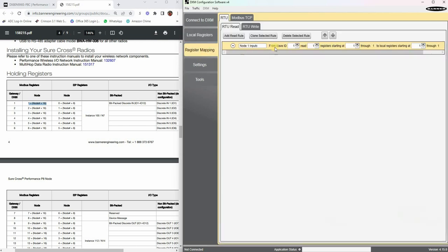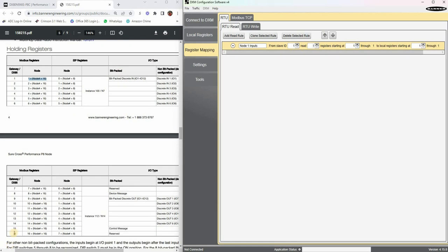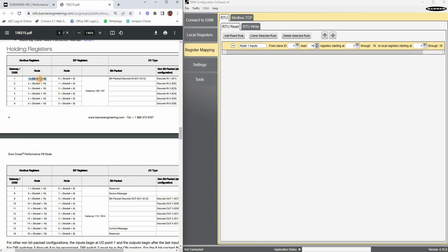So we're going to keep everything at 1 right now. Slave ID 1. We're going to read, looks like we have 16 total registers, we're just going to read all of those so we're going to type in 16 here. And then we're going to start at this address that's on the data sheet for those inputs. They actually start at this address right here. So if my node number is number one, then I'm going to times that times 16 and I'm going to add 1, and that's going to give me a value of 17. That's my starting address and notice that it goes in order, consecutive order to number 32.